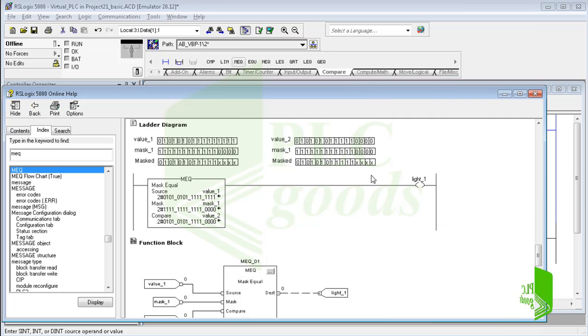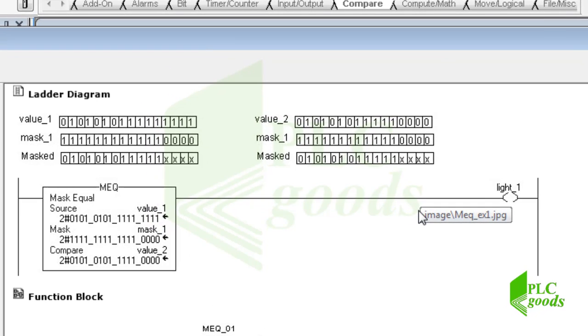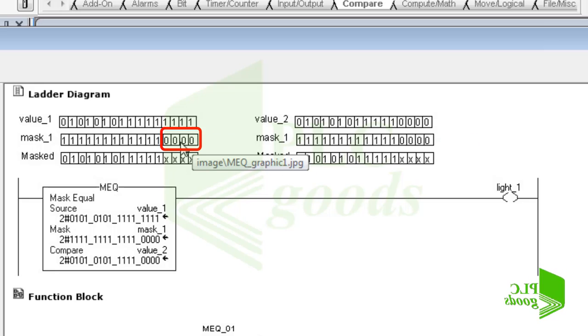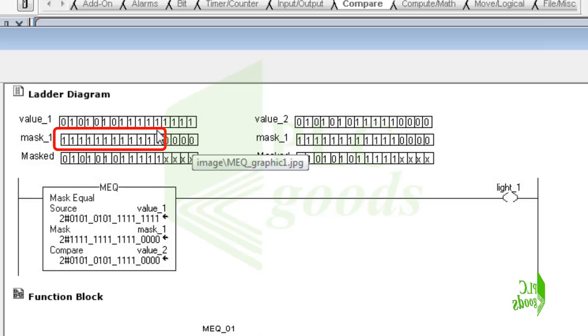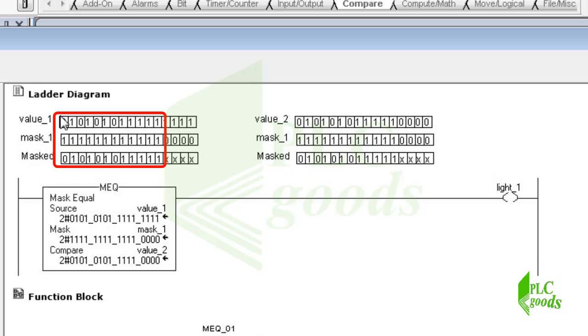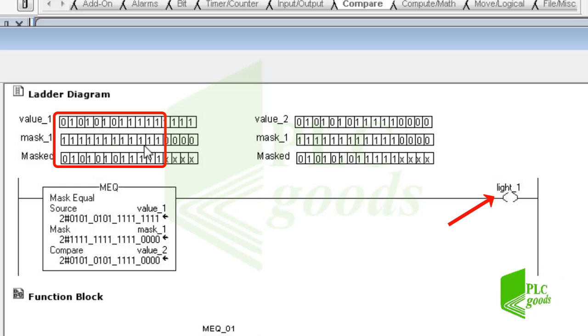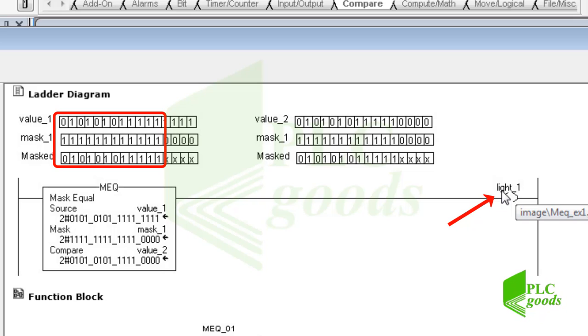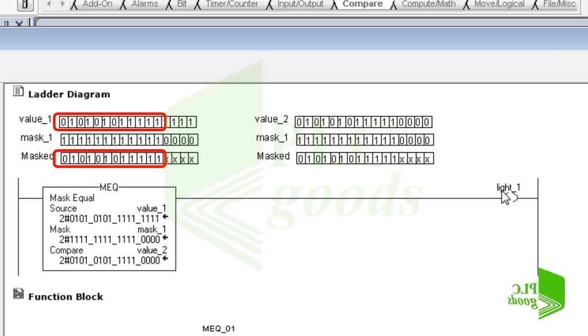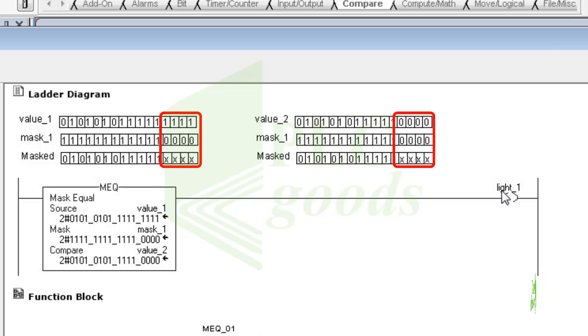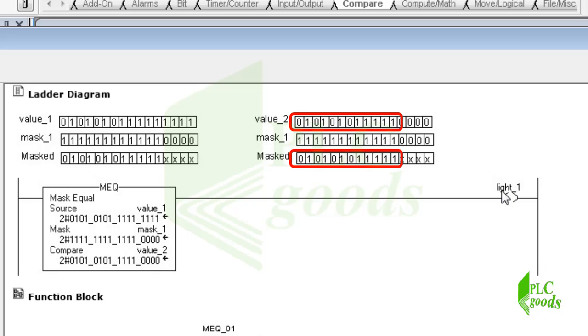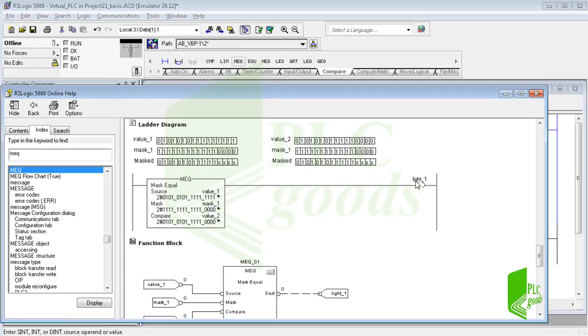Let me use this example, that the three numbers are entered in binary form. The second one is the mask number. A zero in the mask means the data bit is blocked. A one in the mask means the data bit is passed. So if these bits of the first and third numbers are equal, this instruction sets the output light_1. Otherwise, this output will be off. This example shows that the masked values are equal. As you see, a zero in the mask restrains the instruction from comparing that bit. So for the right state, the output will be on too.